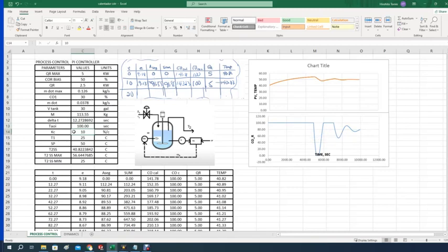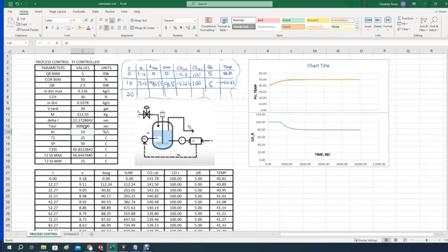So I'd rather have a value close to 3000. I want to put 3000 here on the tau I. Again, very smooth, I would say. So 3000, and the system within an hour, less than an hour, was right there at the set point. And I can say about the 5000, it took a little bit longer, but not a big deal, you know.